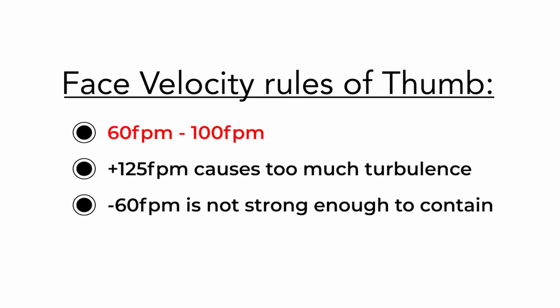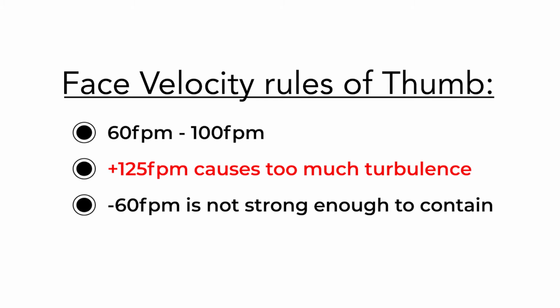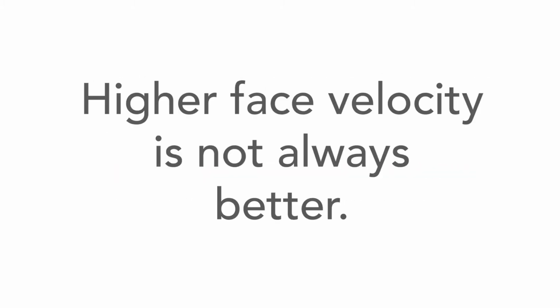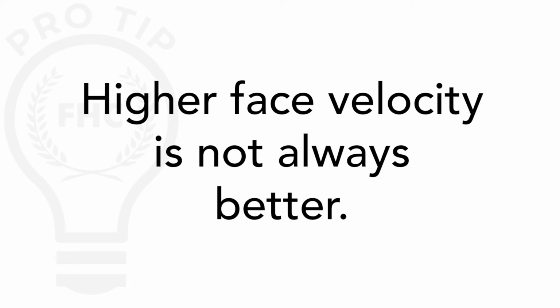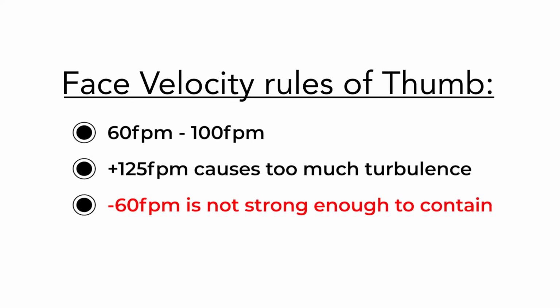You should only work at a fume hood that has a velocity alarm and the velocity is within the specified range. Here in the U.S., you will find that hoods were designed to operate between 60 feet per minute and 100 feet per minute. Occasionally we'll find hoods with higher or lower design velocities. While 100 feet per minute has a logical basis, as the face velocity goes higher, particularly over 125 feet per minute, excess turbulence is created, reducing the hood's ability to contain. So more isn't necessarily better. And too low, you're more likely to have external movements cause loss of containment.